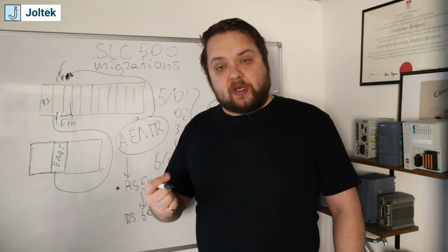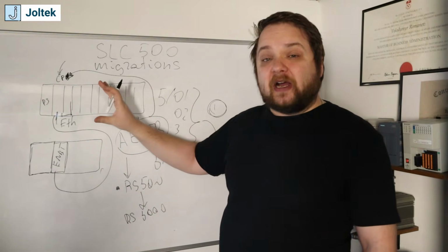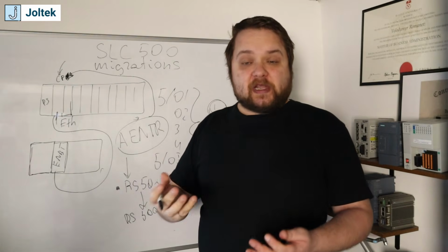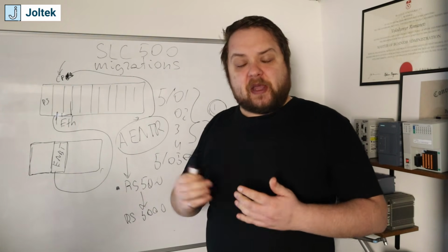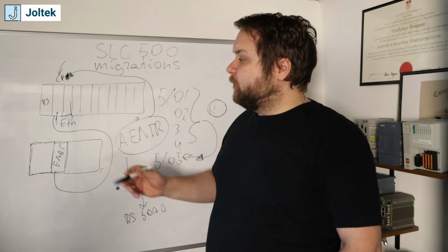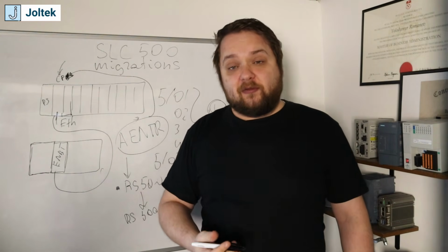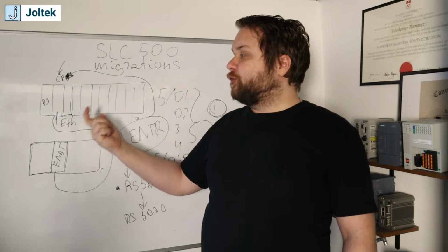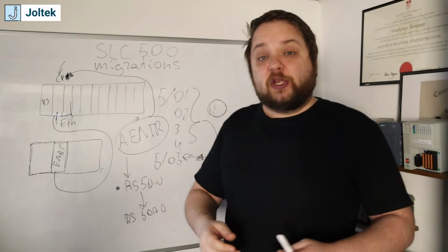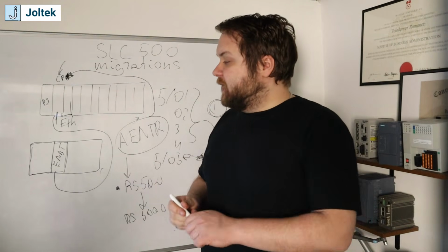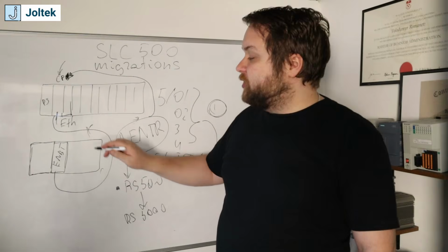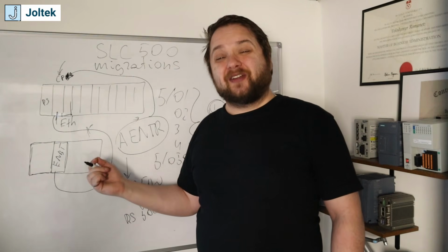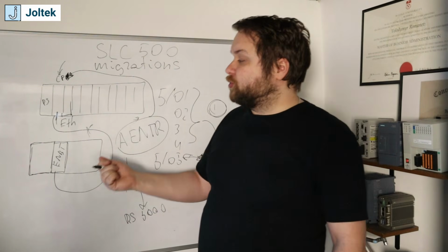Now, it is important to realize that depending on your process and environment, it might be critical for you to have this as a standalone rack. For example, if you're going to work in any chemical or food and bev plants, it is possible that you have a skid that needs to be powered down for CIP, for example, or you have a skid that's going to be relocated. A lot of those earlier racks were on movable equipment, and so what you will run into, if you cut this controller communication cable, is a lot of different faults, and if you don't handle them properly inside of your PLC, you're going to run into trouble.